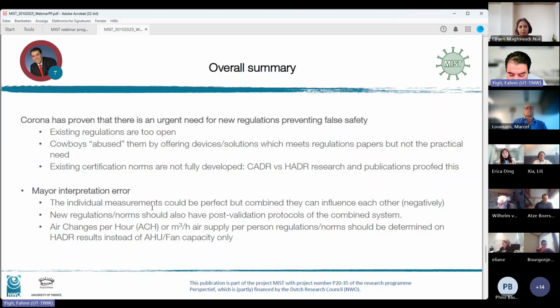For HVAC systems, what's wrong with having, next to the paper of the air handling supplier who measured literally the air flow of the inlet grids, also a hygienic air delivery rate test conducted? That gives you a post validation to see what the real value is.